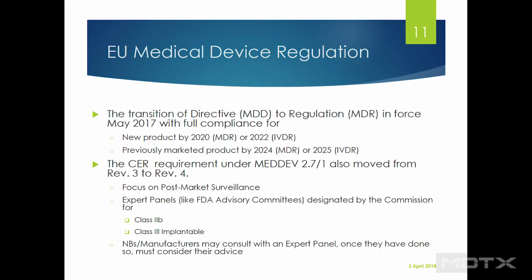And this is in relation to what's now required under the CER. So focus on more post-market surveillance, requirement for expert panels. I'm talking about this in the context of the CER, but this is really for device approvals into the market overall as well. So there's a correlation, and Anne's going to do a better job of teasing that apart for you and giving you the distinction between seeking market approval versus maintaining your CER. But these are the kind of changes that are really impacting both.